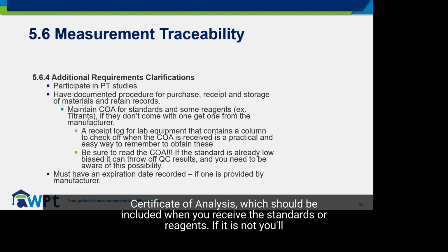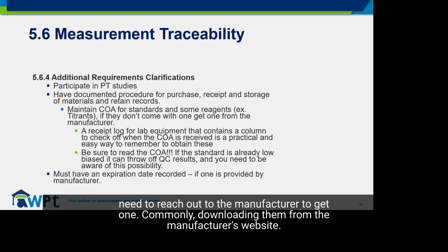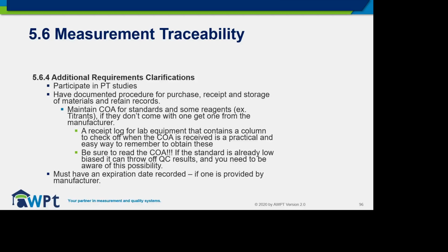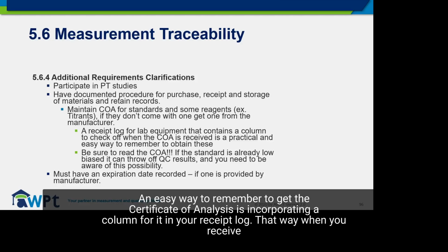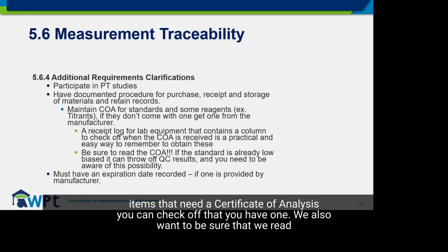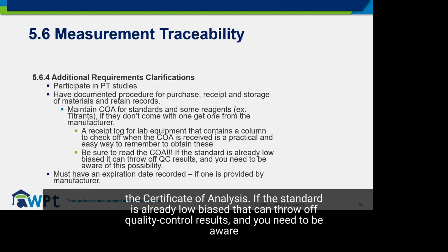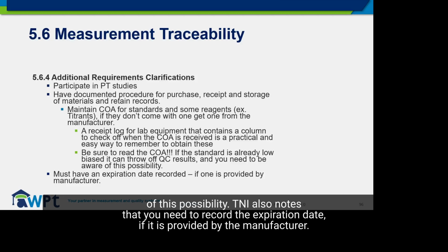This will mainly be the certificate of analysis, which should be included when you receive the standards or reagents. If it is not, you'll need to reach out to the manufacturer to get one, commonly downloading them from the manufacturer's website. An easy way to remember to get the certificate of analysis is incorporating a column for it in your receipt log. That way, when you receive items that need a certificate of analysis, you can check off that you have one. We also want to be sure that we read the certificate of analysis. If the standard is already low biased, it can throw off quality control results, and you need to be aware of this possibility. TNI also notes that you need to record the expiration date if it is provided by the manufacturer.